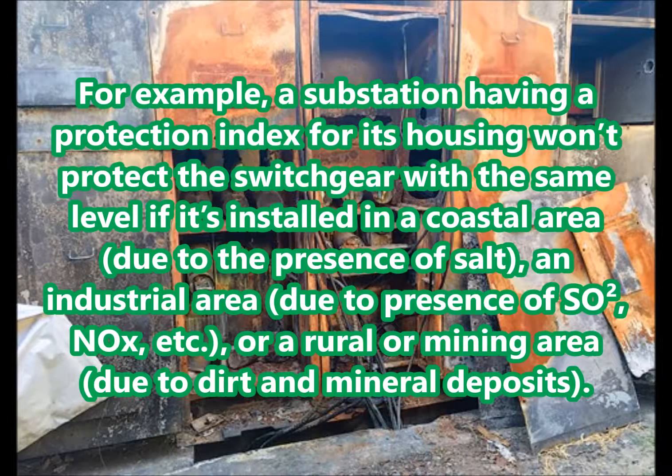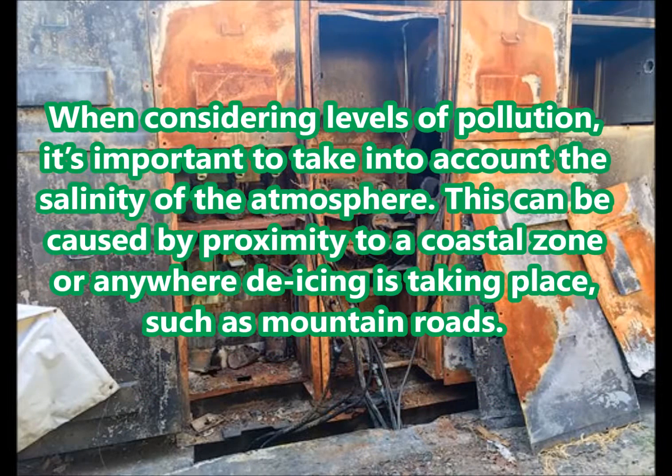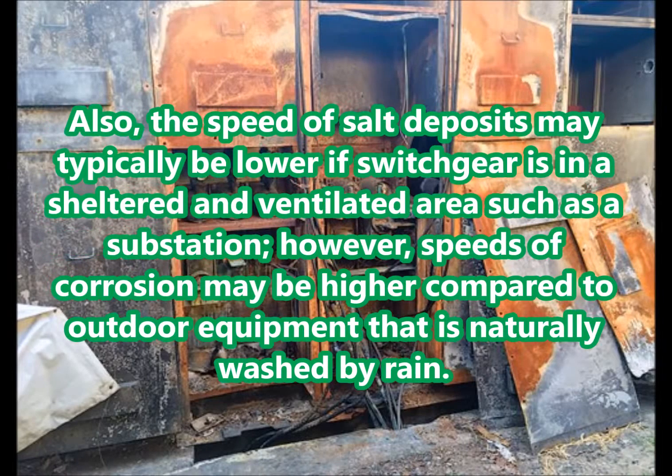For example, a substation's protection index for its housing won't protect the switchgear at the same level if it's installed in a coastal area due to the presence of salt, an industrial area due to the presence of SO2, NOx, etc., or a rural or mining area due to dust and mineral deposits. When considering levels of pollution, it's important to take into account the salinity of the atmosphere. The speed of salt deposits may typically be lower if switchgear is in a sheltered and ventilated area such as a substation; however, speeds of corrosion may be higher compared to outdoor equipment that is naturally washed by rain.